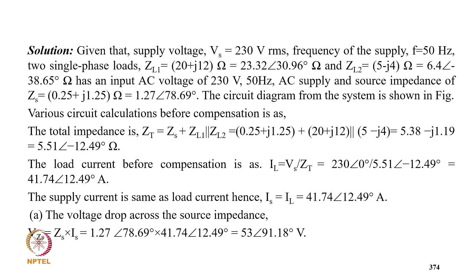The given system configuration can be simplified using the Thevenin equivalent circuit. The value of Thevenin voltage and impedance: VTH equal to Vs into ZL2 upon ZS plus ZL2, so it comes to 248.49 at the angle minus 11.01 degree volt, and ZTH equal to Zs in parallel with ZL2, which comes to 1.38 at the angle of 67.70 degree.